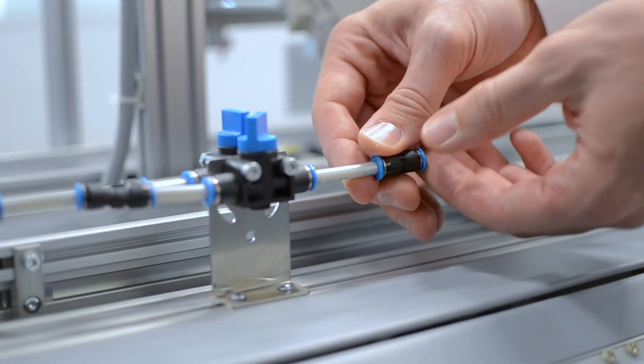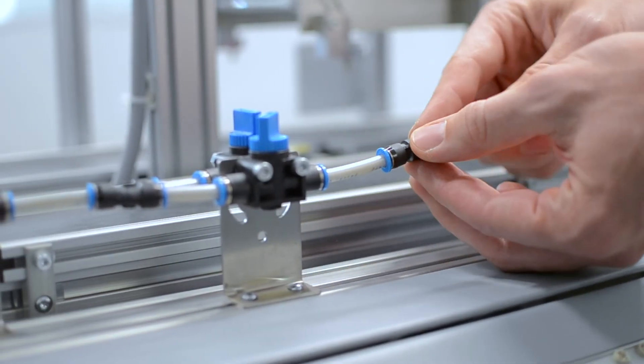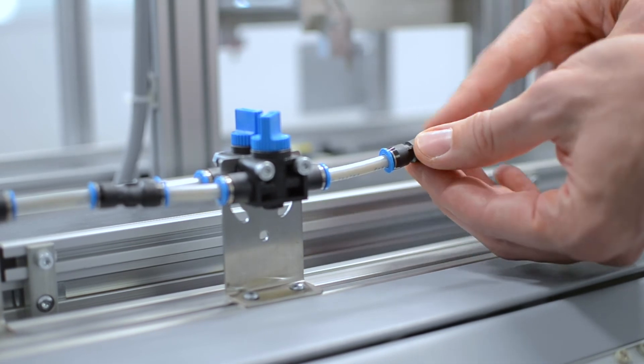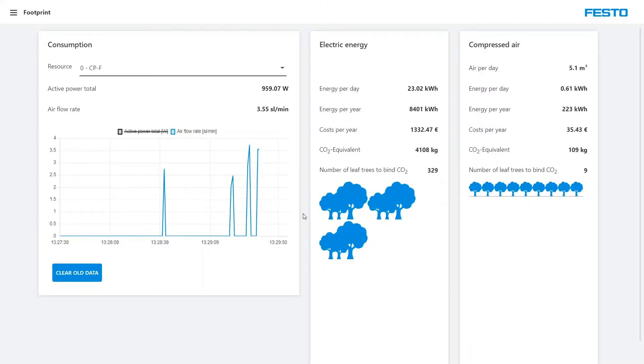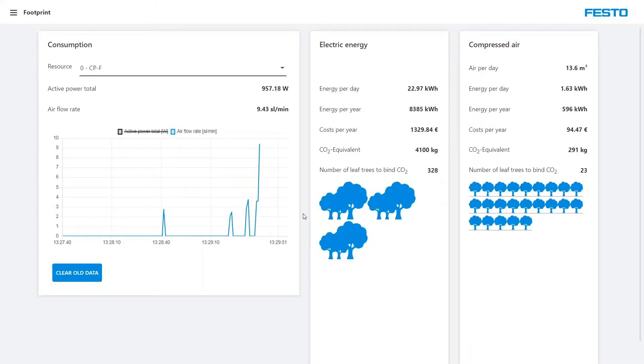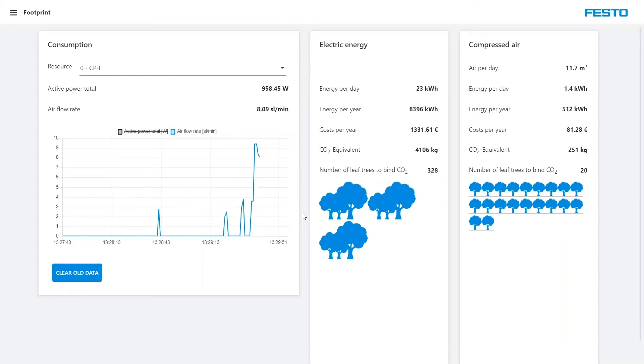Another example: compressed air escapes at this point, a typical leakage. Is this leakage relevant for the efficiency of the machine? A look at the dashboard illustrates that the costs exceed the typical compressed air costs many times over. Repairing this leakage is therefore highly effective, and it is also good for the environment.